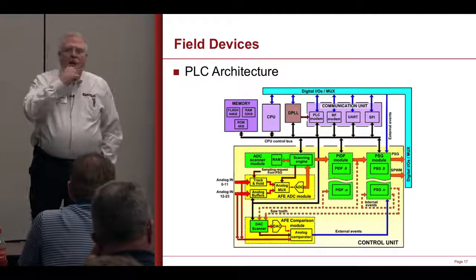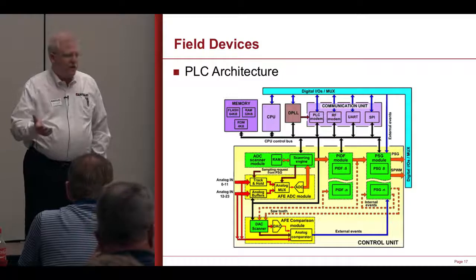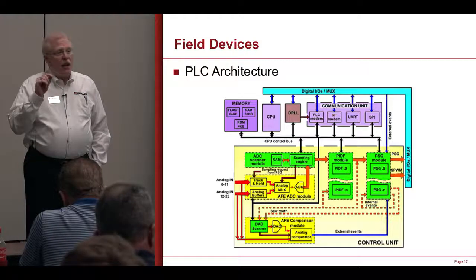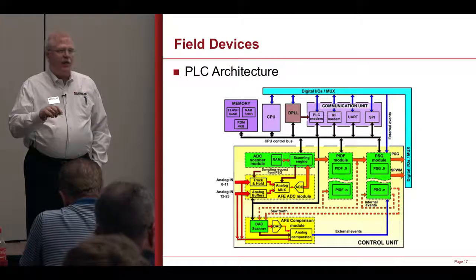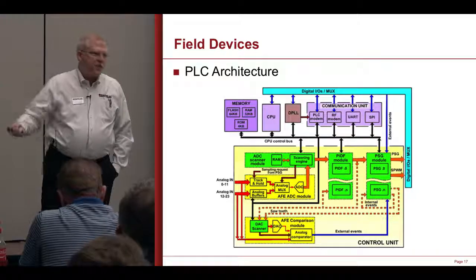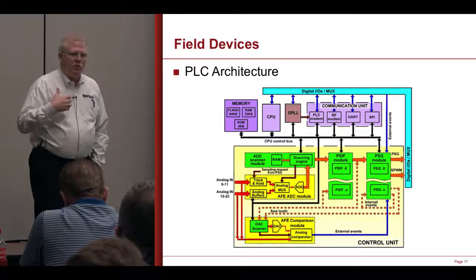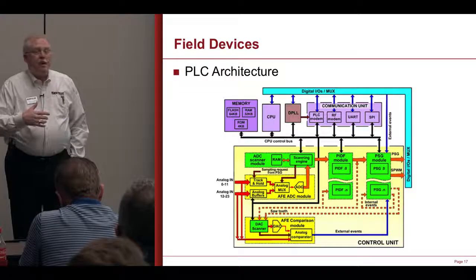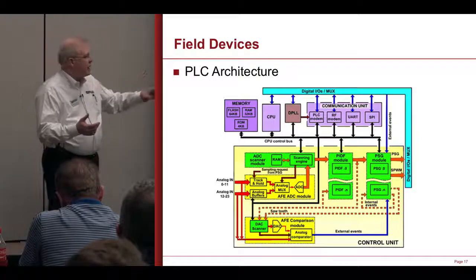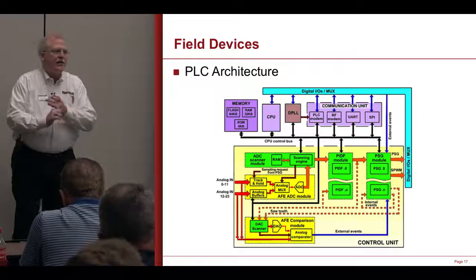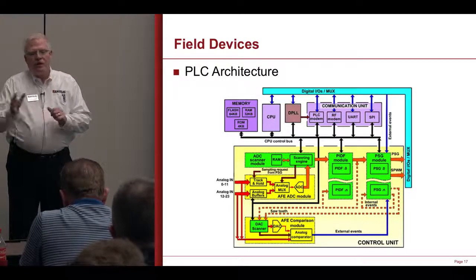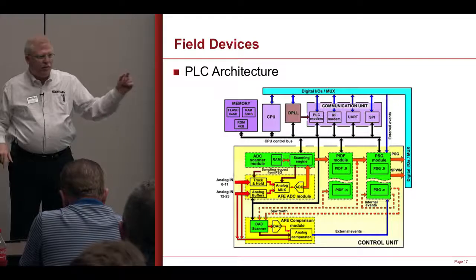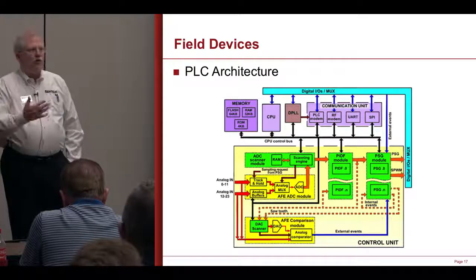There's also advanced processing. You can tell a PLC — say it's running a gas storage facility — that when injecting gas it should alarm and control things one way, and when withdrawing gas, alarm and control things differently. Different things are important based on operating mode. I can also do first-in, first-out programming — if I get this trip first I'll do this, and if a second trip comes in it has a precedence unless I'm in a certain operating condition. A lot more capability.